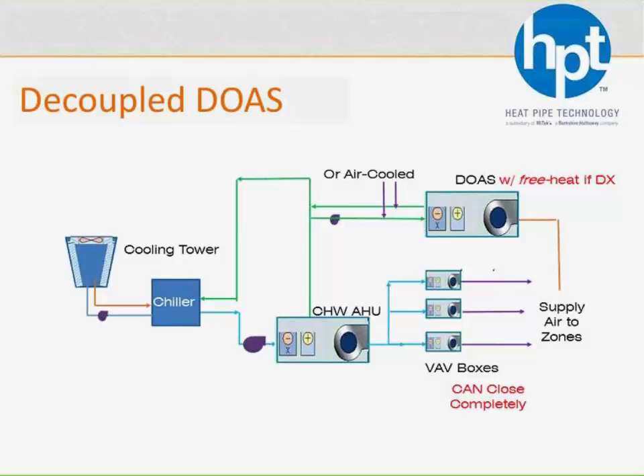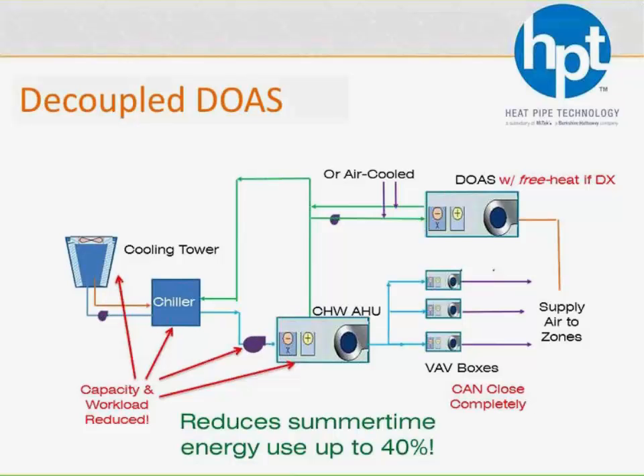Another benefit is those VAV boxes can now close completely because you're not worried about not delivering enough ventilation air. It's being handled by its own DOAS unit. So you can close those completely, and that allows you to not, what they call, over-air the system. You're truly monitoring the amount of outside air that's needed and just adding the recirculation air as needed to control the temperature out in the space. And when you're not having to cool more outside air than is necessary, you're able to reduce your cooling load by quite a bit. So whether we're talking the chiller, the cooling tower, the pump, everything gets reduced. And you generally find that in the summertime that energy is able to get reduced by up to 40%, which is quite a hefty number.